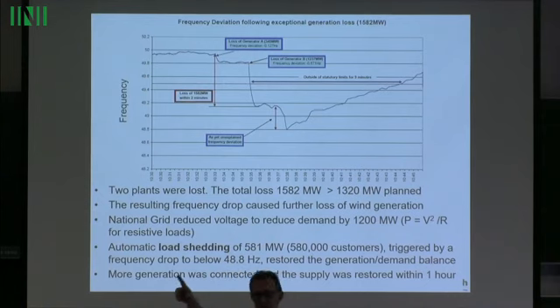If you had a wind turbine connected to that part of the distribution network, it would still operate and produce electricity, but you need people to go out and check the line, and they can't have an active energy source there because they'd be electrocuted. So wind turbines have this rate of change of frequency (ROCOF) protection, which senses when frequency suddenly changes. If it changes suddenly like that, it means there's a danger that part of the network was islanded, and if so, they need to switch off that generation.